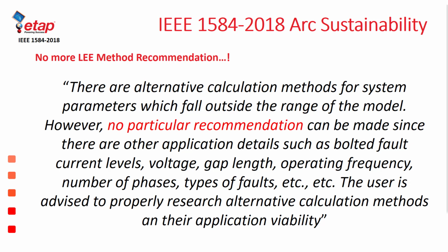Well, there is something that is actually particularly exciting to me, since I've had to deal with the repercussions of previous recommendations made in the IEEE 1584-2002 standard, in particular the application of the Lee method for voltage levels above 15 kV. Well, in the IEEE 1584-2018 guideline, there is no more Lee method recommendation. Instead of that, we have the following recommendation. Let me read it for you guys.